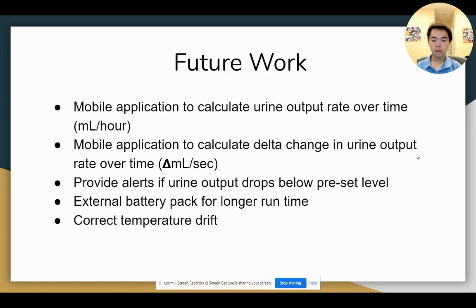We would also like to correct the temperature drift. In most clinical settings, there is no temperature drift because the temperature is maintained very constant. However, in a non-clinical setting, or if the temperature isn't controlled, there can be a drift in the readings. Obviously, we want to fix that, so we would do that by using a compensating strain gauge to correct any potential drift.